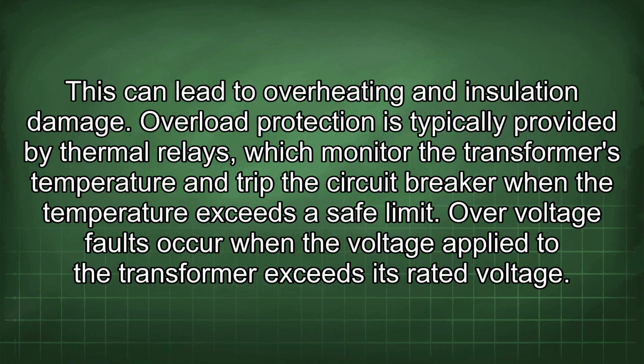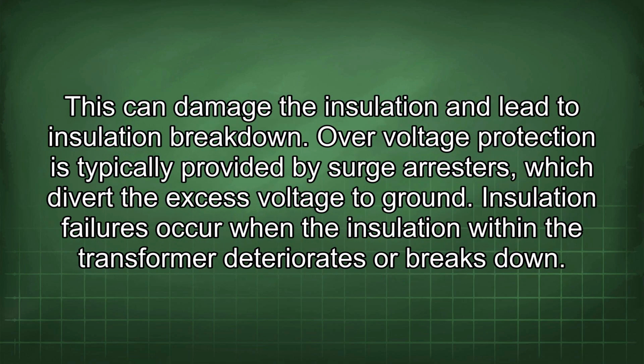This can lead to overheating and insulation damage. Overload protection is typically provided by thermal relays, which monitor the transformer's temperature and trip the circuit breaker when the temperature exceeds a safe limit. Overvoltage faults occur when the voltage applied to the transformer exceeds its rated voltage. This can damage the insulation and lead to insulation breakdown. Overvoltage protection is typically provided by surge arresters, which divert the excess voltage to ground.